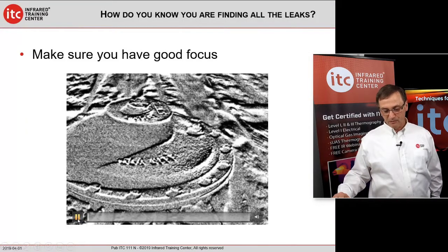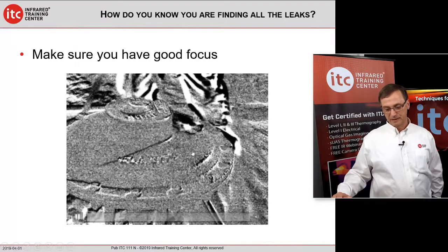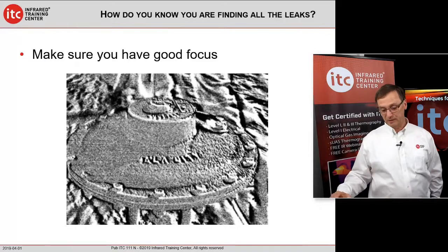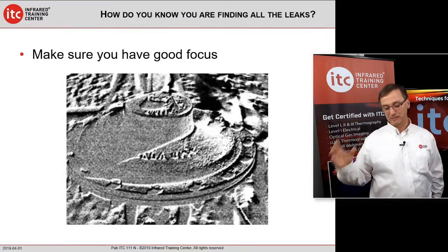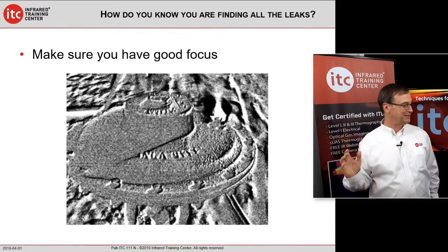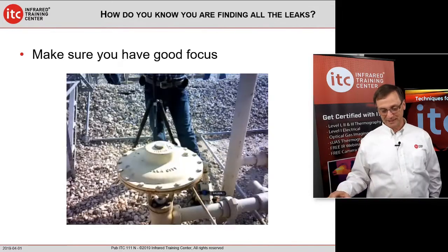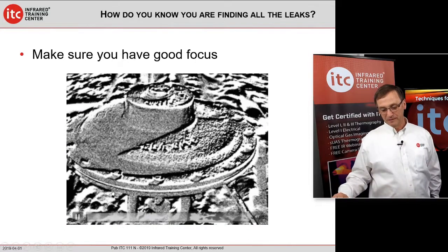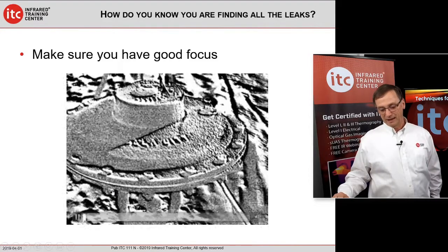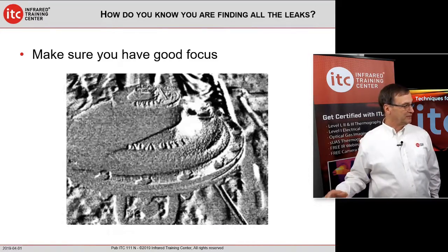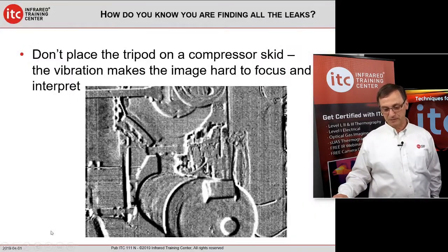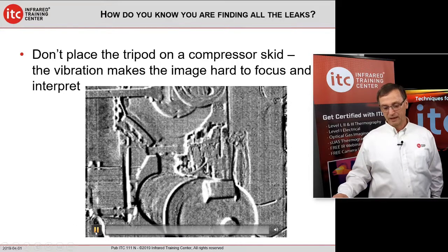And make sure that you have really good focus. And this is the top of another gas operated or air operated valve. High sensitivity mode, handheld, I'm not a fan of. But I don't do this on a daily basis. I don't do the inspections on a daily basis. The little leak was right there, and very hard to hold that camera steady. The HSM is best when the camera is steady, but you can clearly see the leak, and it was great focus for the customer who took that video.